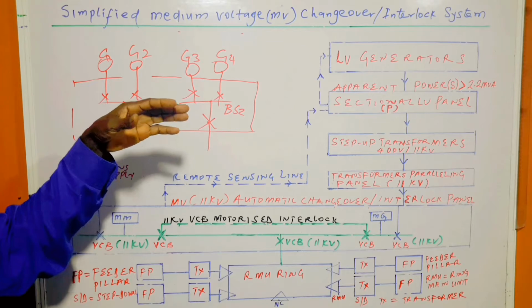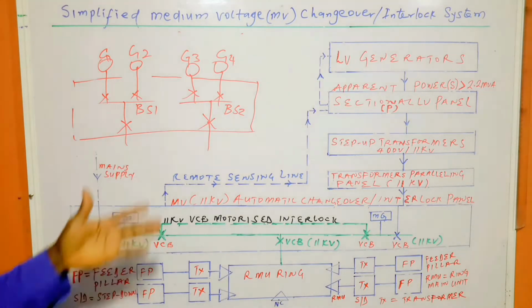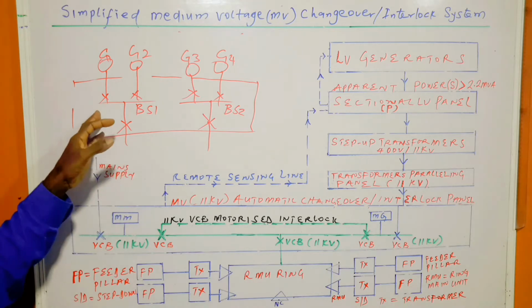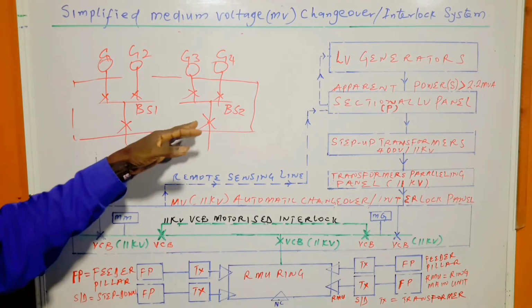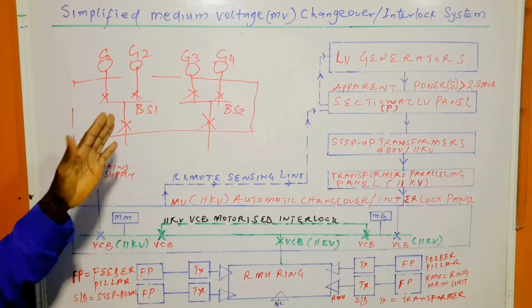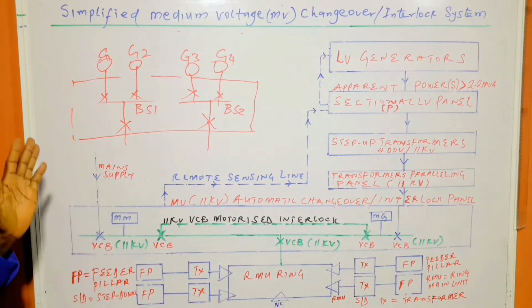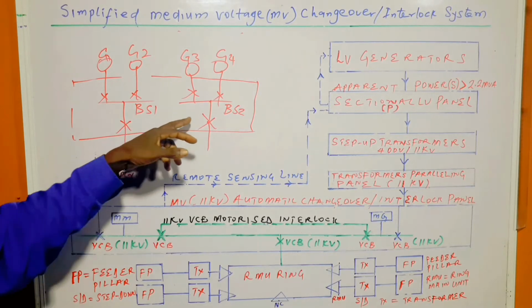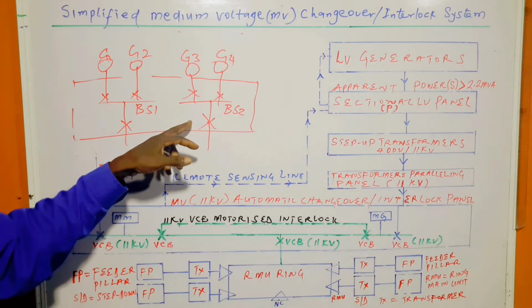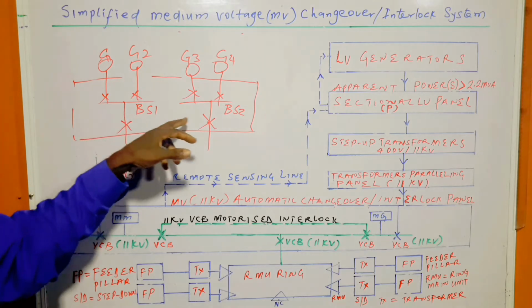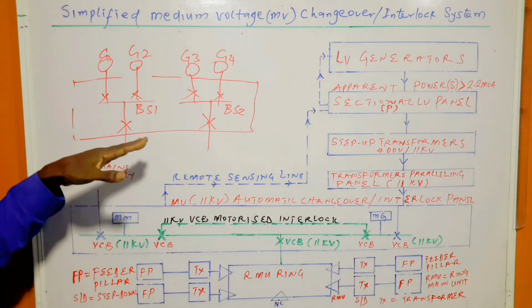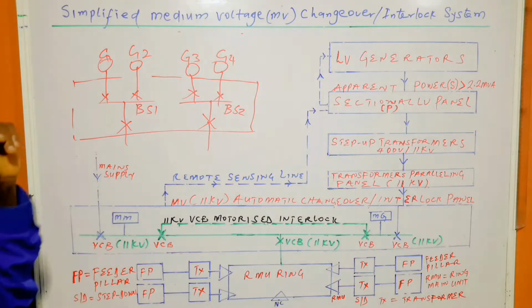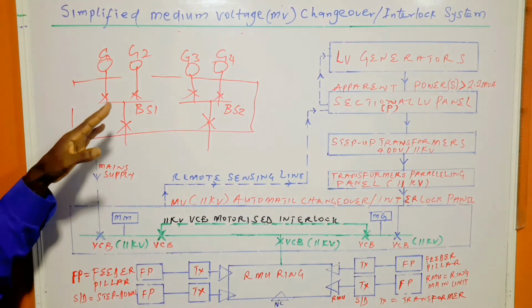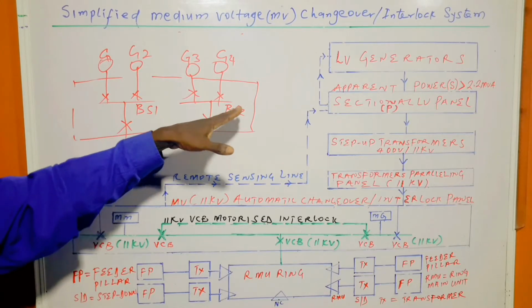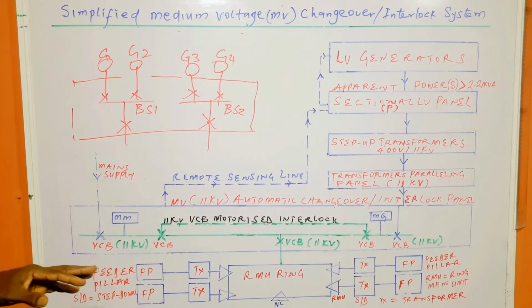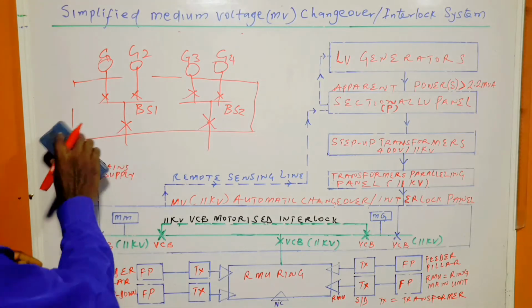If the power is very big, then you can decide to have more sections, in order to divide the current into sections that the circuit breakers will cope with. Using these two circuit breakers to control the current is easier than looking for a single one at low voltage, and that is why the sectional LV panel is brought into this situation.